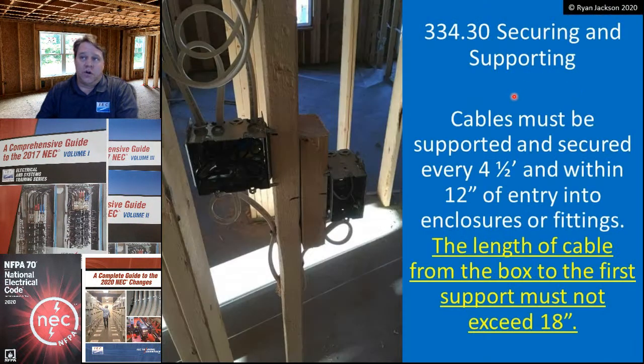New to the 2020 code, we have this clarification. Cables have to be supported and secured every 4.5 feet and within 12 inches of entry into the enclosures or fittings. Now that's been in the code for a long time, but how do you measure that 12 inches? It was clarified in the 2020. The length of the cable from the box to the first support must not exceed 18 inches of cable length. So this cable, as the crow flies, needs to be secured within 12 inches and 18 inches of cable length.